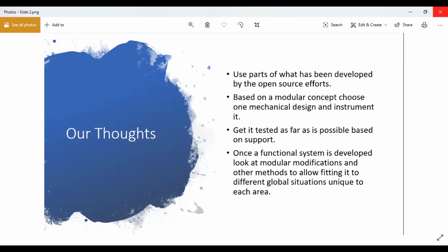The more I learned about the physiology of the lung, the more I realized that this was a lot more complicated than just articulating some kind of an accumulator device, like an ambu bag or some kind of a pneumatic bag. But we can control tidal volume. We have max pressure, essentially a pop-off valve, check valves, and all those sort of things. Some of those are actually subcomponents of the more sophisticated ambu bag, so they're pretty easy to accomplish.